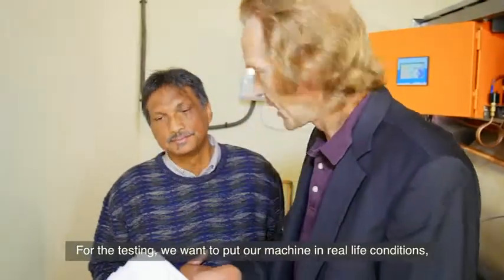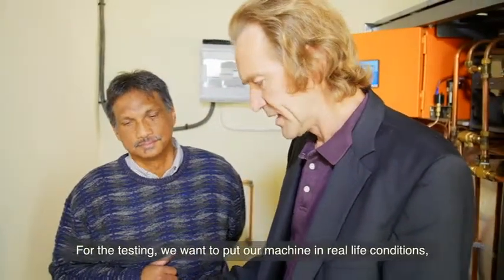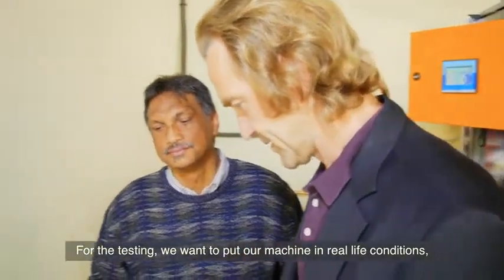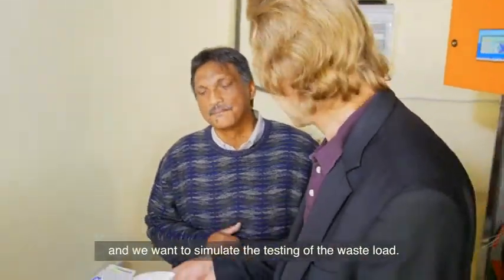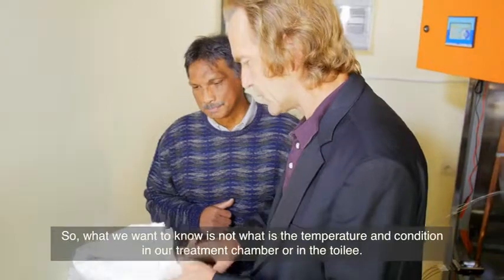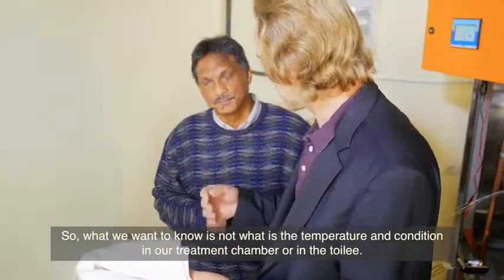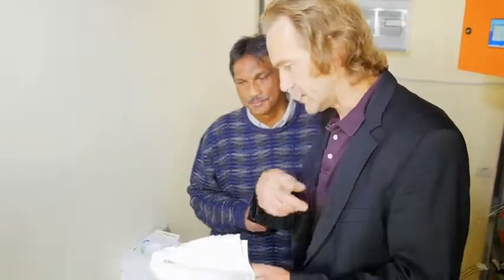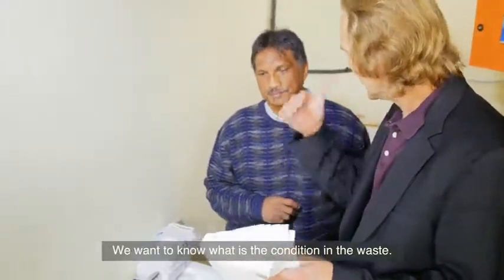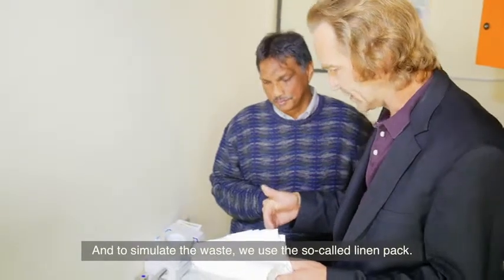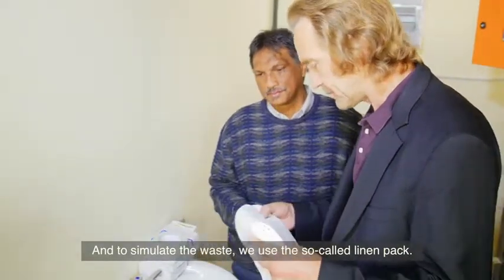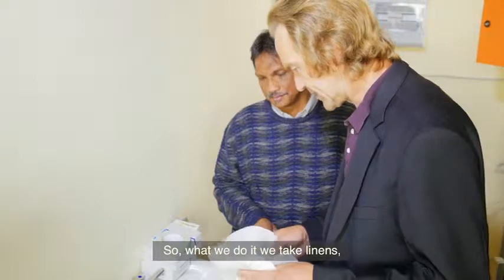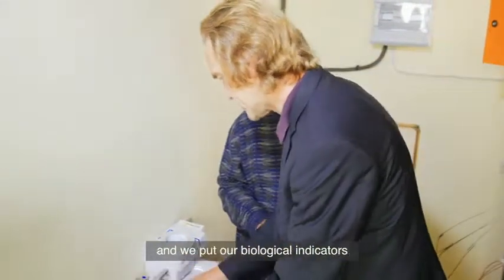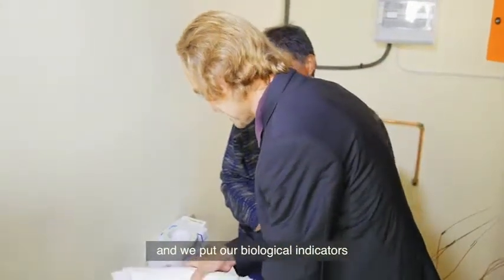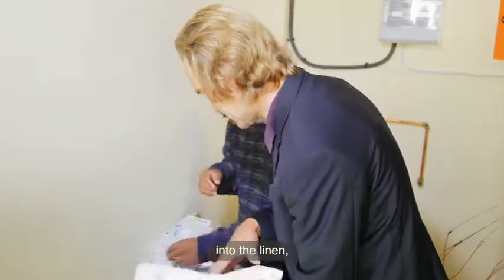For the testing, we want to put our machine in real life conditions, and we want to simulate the testing of a waste load. So what we want to know is not what is the temperature and condition in our treatment chamber or in the trolley. We want to know how is the condition in the waste. And to simulate the waste, we use a so-called linen pack. So what we do is we take linens and we put our biological indicators into the linen.